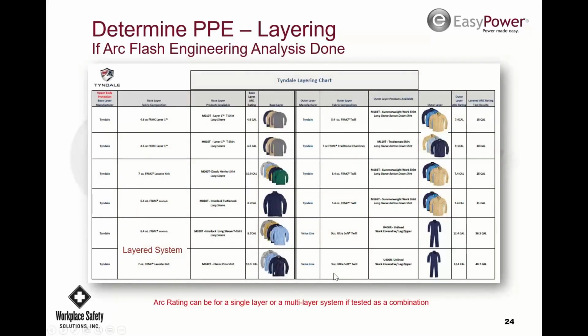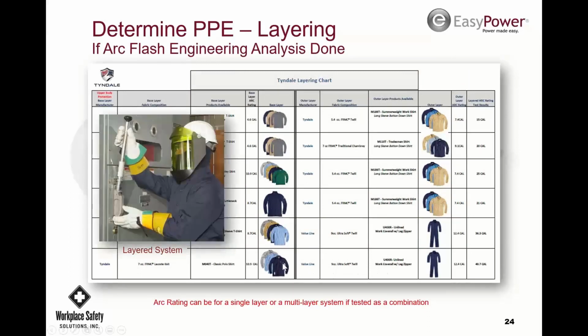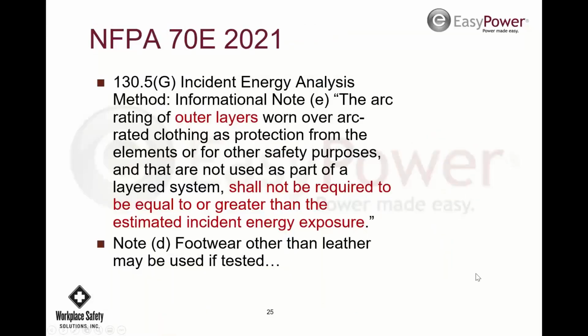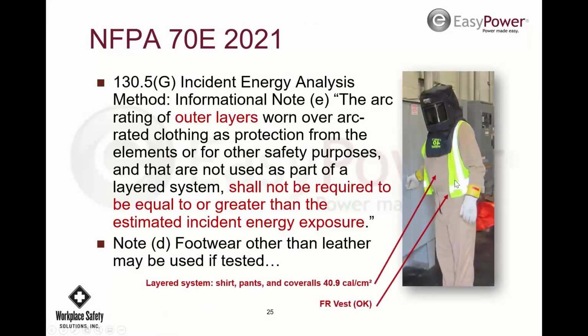All right, so, and this is a layering chart with NFPA, with Tyndale, the company that I use for my clothing. So I'll put these two together, and I'm at 10.4 calories. 12.4 plus 10.9 equals 23.3, tested as a system at 40.7. This is a new 2021. The outer layer no longer needs to be fully arc flash rated. So this is FR rated and it's fine, but it's not giving me arc flash protection. It just won't flame up.